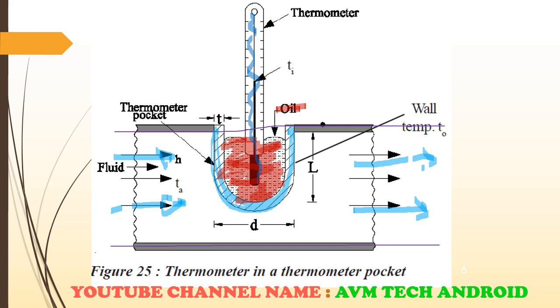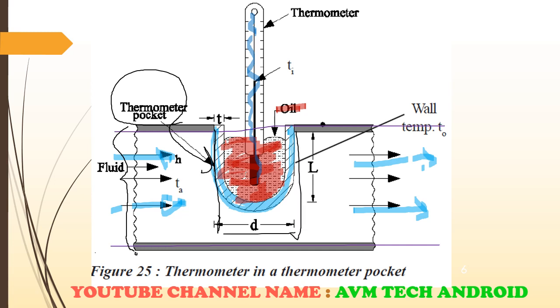So quickly we will go through this figure. You can see the thermometer pocket. The fluid is flowing through this pipeline. D is the outer diameter of this pocket. t is the thickness of this well. L is the length of this well. T0 is the wall temperature. Fluid is flowing with temperature Ta. Ti is the temperature indicated by the thermometer.